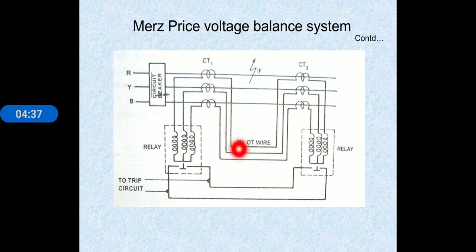At that time, under faulty condition, the equivalent circulating current will flow through the pilot wires and the operating coils of this relay. In normal conditions there is no current, as the voltages are equal in both secondaries of the current transformers. But whenever a fault occurs, the secondary voltages become unequal, and current is allowed to flow through the relays.